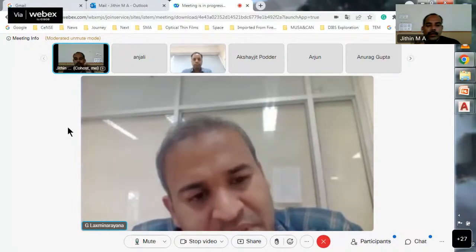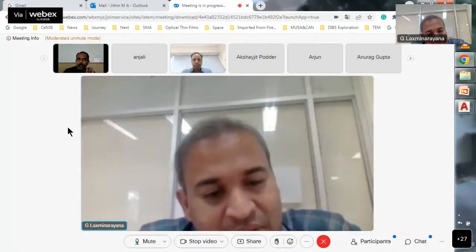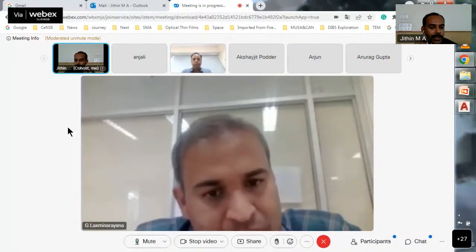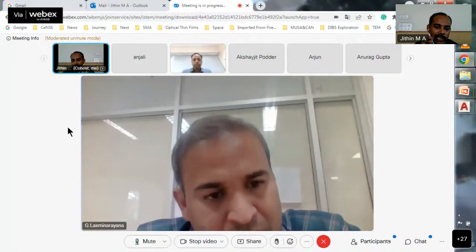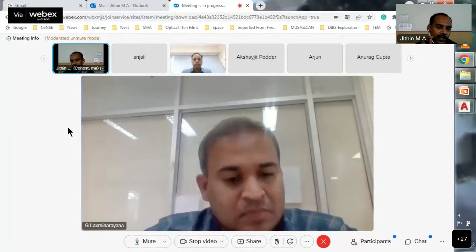Is that again the pressure rise per unit volume, or for a given volume? That calculation I don't have with me right now. I know there is a calculation for that. With a helium leak system we cannot do that, because it is only showing the rise of helium, but actually it is not only helium that rises, all gases are present. So we have to use RGA for that purpose to see what gases are increasing and how much, p1, p2, p3. We have to do that calculation. There is a formula for that, and I think I can share it with you. There are different slides for that.